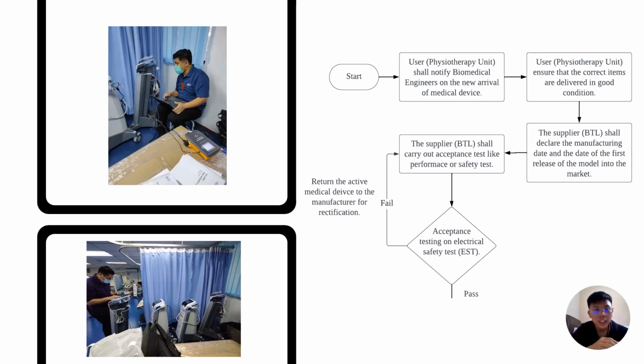After that, the supplier, which is the BTL company, shall declare the manufacturing date and date of the first release of the model into the market. The supplier shall also carry out the acceptance tests like performance and safety tests. After that, they shall perform the electrical safety test on the devices. If the electrical safety test fails, we have to return the medical device to the manufacturer for rectification.